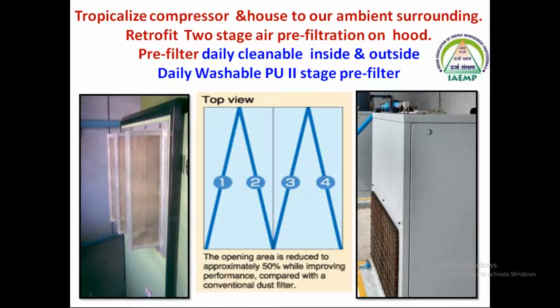That is why one monitors the loss across the filter and suggests the industry go for a V-type filter, a 30 degree V-type filter. The orientation of the V-type is 30 degrees, so that you can increase the area of coverage of the intake, and you will have a PU mesh to reduce particulate matter in the air. Ultimately, this is daily washable and cleanable in the industry. And the existing main filter, which is a paper filter, can last for 3000 hours. Instead of 3000 Pascal as the pressure drop, you can maintain less than 1000 Pascal at the main filter.